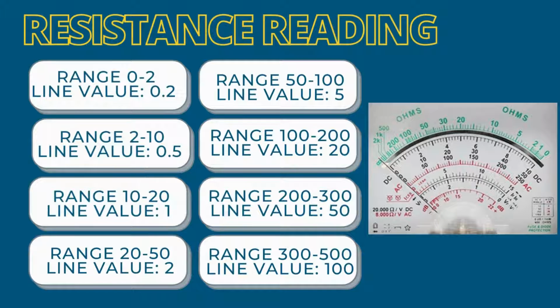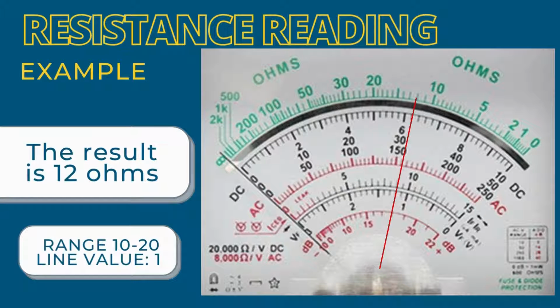Range 0 to 2 has a line value equal to 0.2, range 2 to 10 has a line value equal to 0.5, range 10 to 20 has a line value equal to 1, range 20 to 50 has a line value equal to 2, range 50 to 100 has a line value equal to 5, range 100 to 200 has a line value equal to 20. Range 200 to 300 has a line value equal to 50, range 300 to 500 has a line value of 100, and so on. For example, the pointer points in between 10 to 20. We understood that the value of the line in between the range 10 to 20 is 1. So therefore, the answer is 12 ohms.